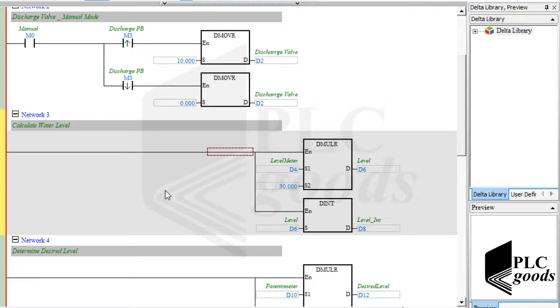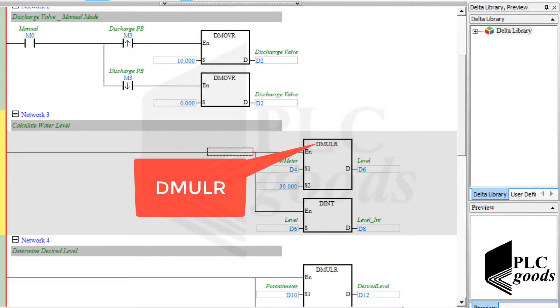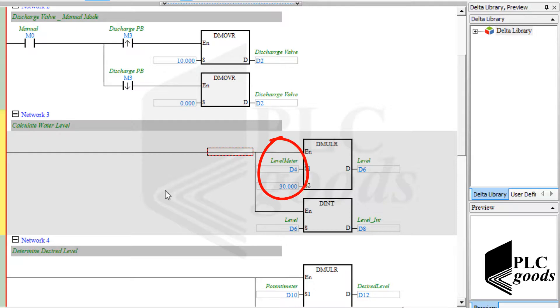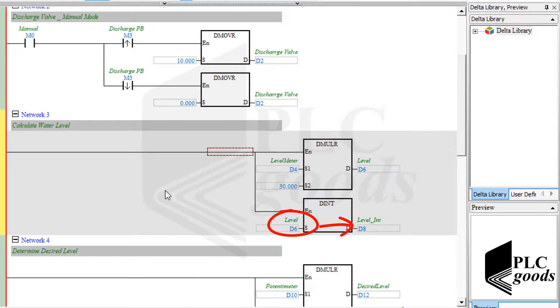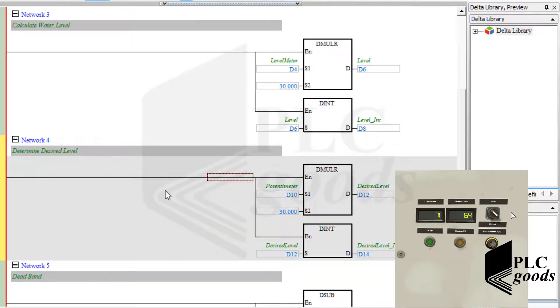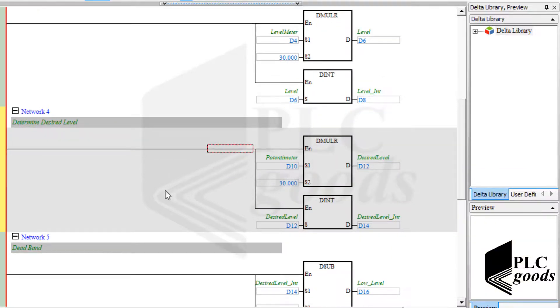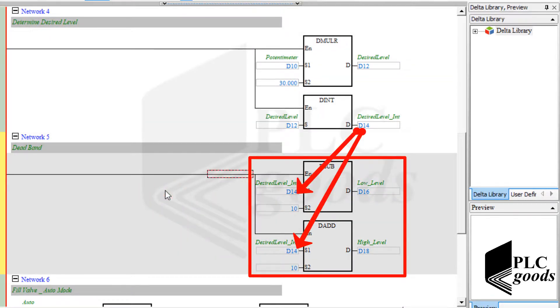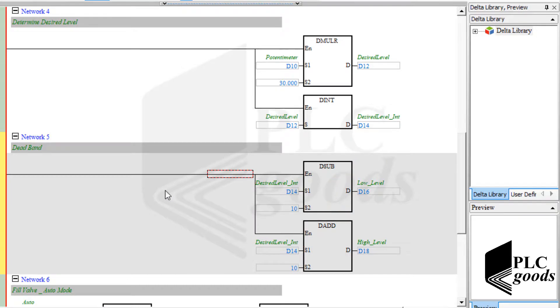For a real number multiplication we must use the real multiply instruction. It works similarly. The third network multiplies the received number from the level meter by 30 to convert it to between 0 and 300. It's still a real number. The next instruction converts it to an integer number that can be displayed by the first digital display. The next network works similarly to determine the desired level and display it on the second digital display. Here, I've added a dead band to the desired level using add and subtract instructions. These values will be used instead of the desired level when the automatic mode is selected.